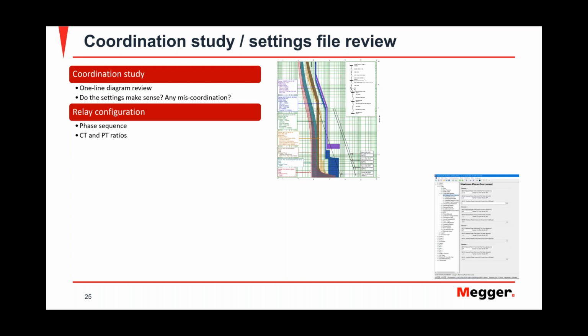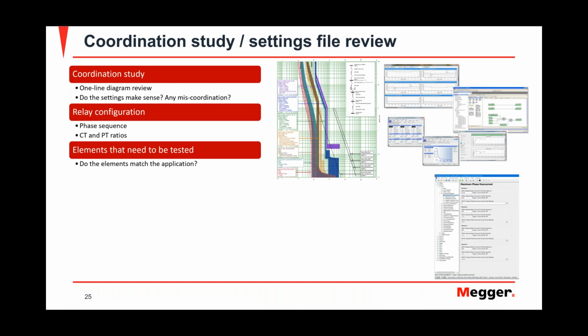The relay configuration. Let's say you have the settings file. That's the polarity on the CTs and the PTs. Are they according to the relay manufacturer? Do they have their recommendation? If they're not, do they make sense? Was that the intent of the engineer? All these are things that just by looking at the drawings you could pick up, and before you're even on site, you have an idea: oh, I'm going to have a problem with this, or I'm not going to have a problem with this.